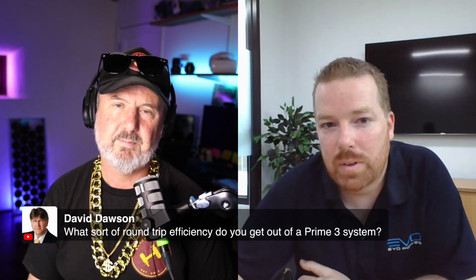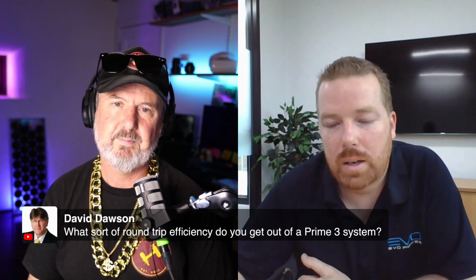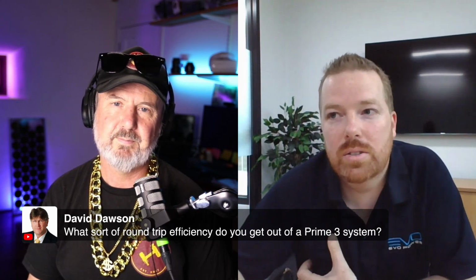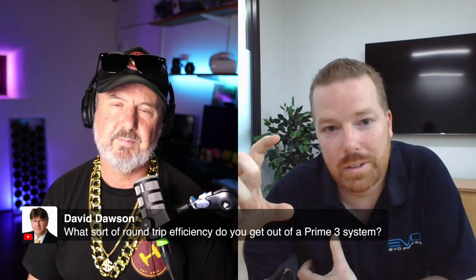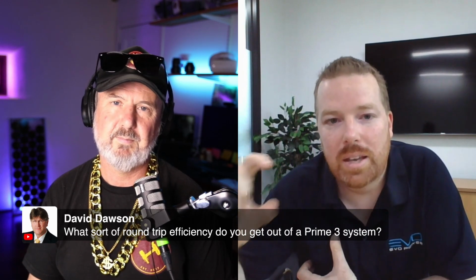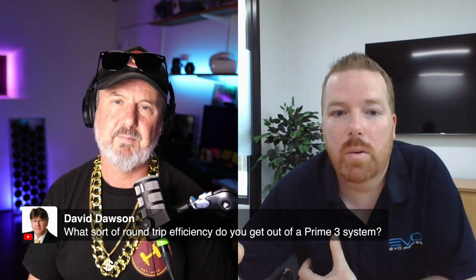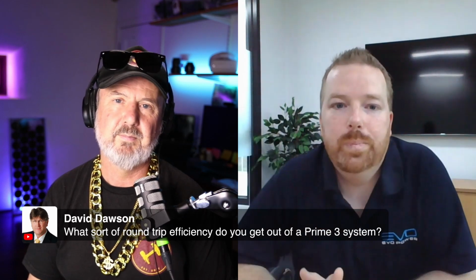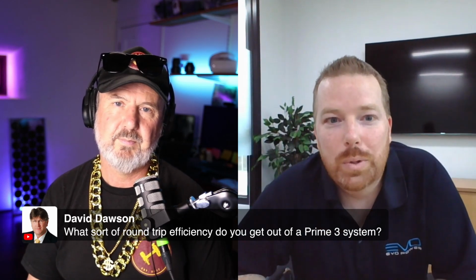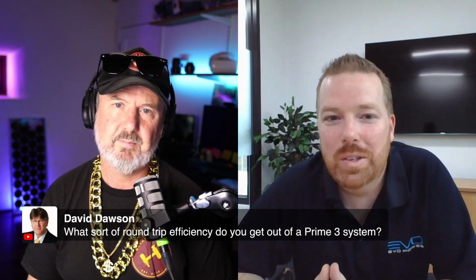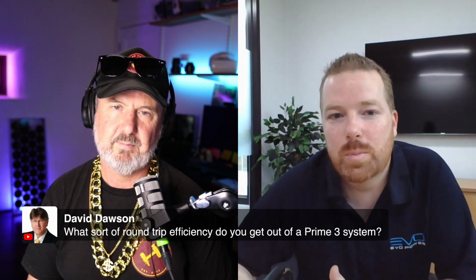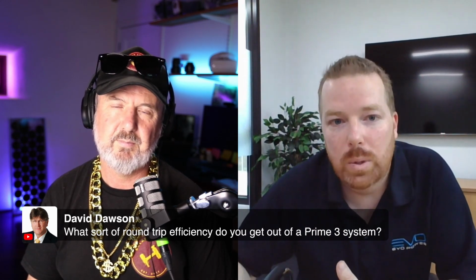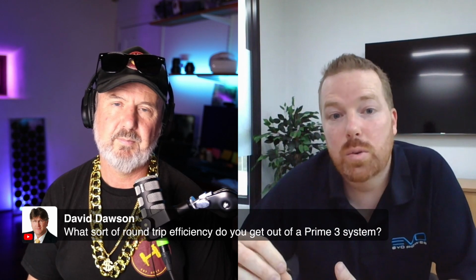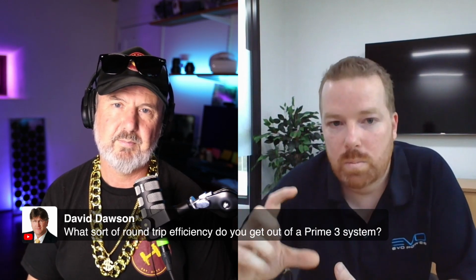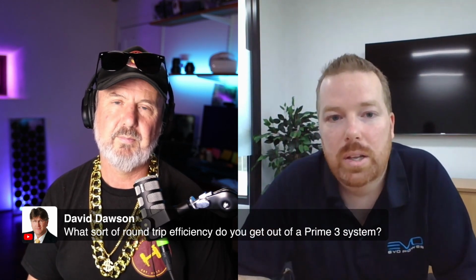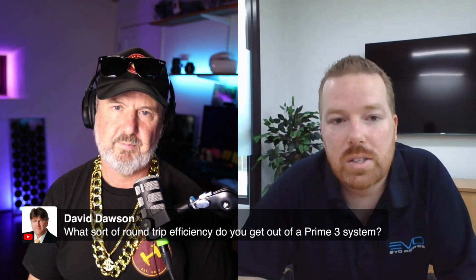The battery modules we have are an OEM version of the battery. So they nominate the nominal value, and then they tell us what the usable is, which is 92% of that nominal value. To put it in simple terms, the battery module we're using within these systems is 6.52 kilowatt hours, and we're using 92% of that, so it's bang on 6 kilowatt hours of usable energy you can access.